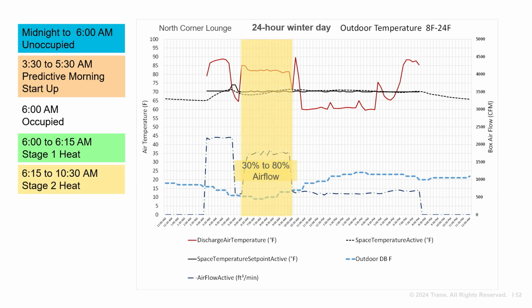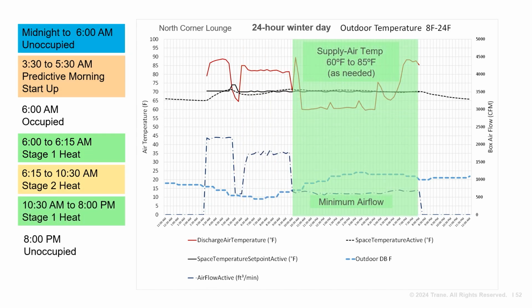During the coldest part of the day, stage 2 heat is needed. Airflow varies between 30 and 80%, with the water valve controlling to 85 degrees supply temperature. Later in the day, back down to stage 1 heat, with the air valve at minimum and the supply temperature varying between 60 and 85 degrees. So on this very cold day, even when nighttime unoccupied setback was used, the room was heated as designed using only 105-degree hot water.